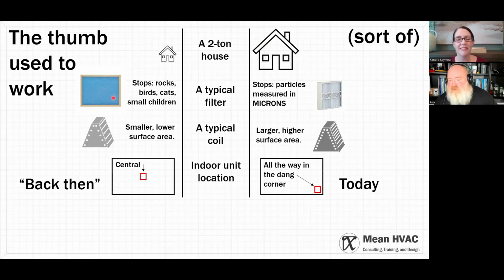We used to have filters that just kept the cat out of the furnace. The filter's job was to keep the coil clean between servicing twice a year. This is not an indoor air quality device, it's a keep-the-coil-clean device. This is what an indoor air quality device looks like, and it chokes up the airflow. You design around that, and they're wonderful, but you forget that air is a small particle that gets somewhat trapped in this media. There are consequences to changing from this to this.